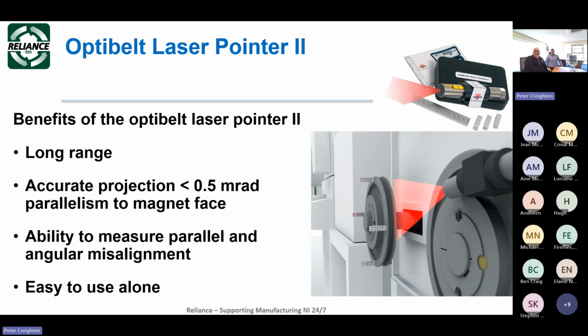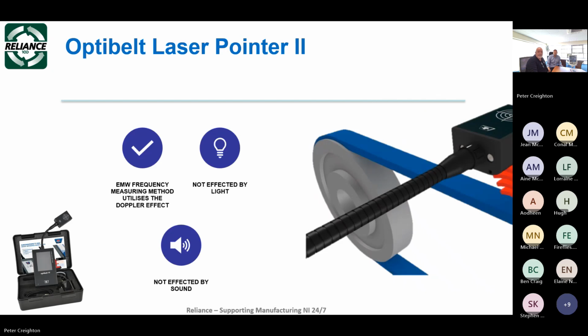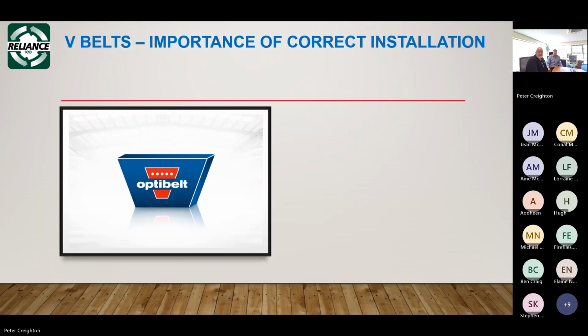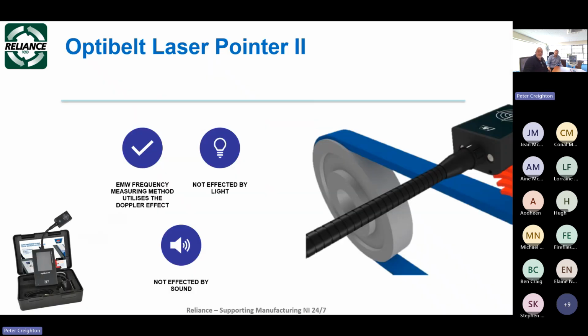This is the benefit of the alignment. If you align your pulleys correctly and your belts are running correctly, the lifetime of your belt is greatly extended because it's lying exactly level on both sides of the groove at all times. Here's our tension kit. How the tension kit works is it's just harmonics. You strum the belt, and it's like tuning a guitar. It'll take the reading back and it'll tell you which is right and which is not.